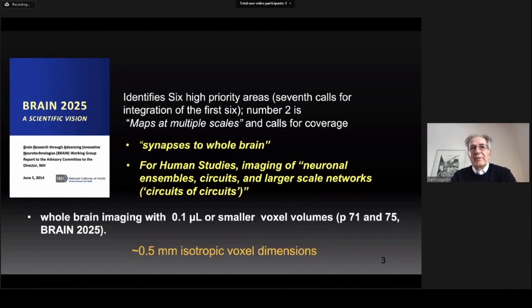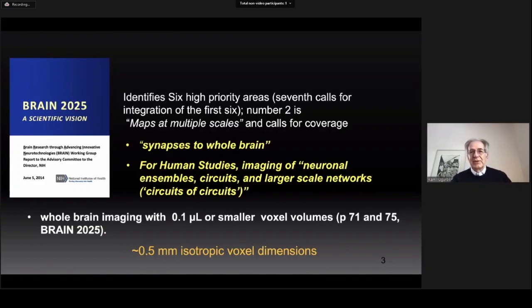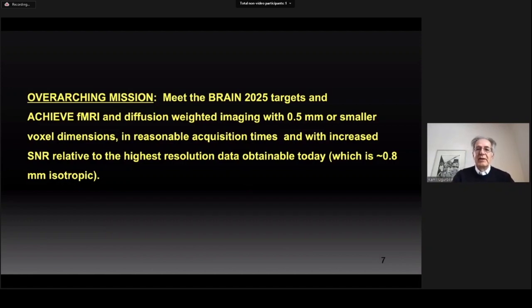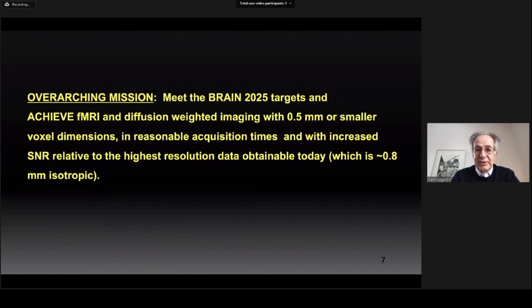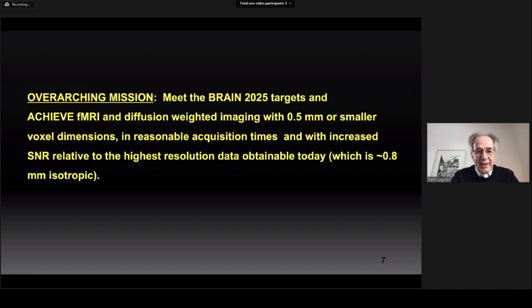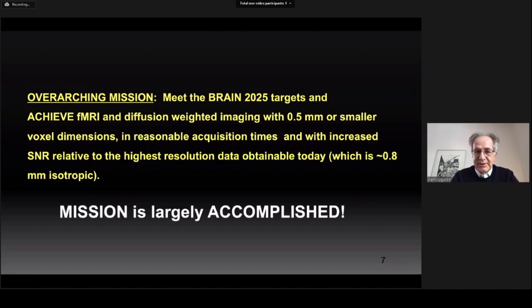Nevertheless, 0.5 millimeter will bring major gains for studying neuronal ensembles that perform elementary computations in the brain. Therefore, the overarching mission of this project is to meet the BRAIN 2025 targets and achieve fMRI and diffusion weighted imaging with 0.5 millimeter or smaller voxel dimensions in reasonable acquisition times and with increased SNR relative to the highest resolution data obtainable today, which is approximately 0.8 millimeter isotropic. I'm happy to say that this mission is largely accomplished.